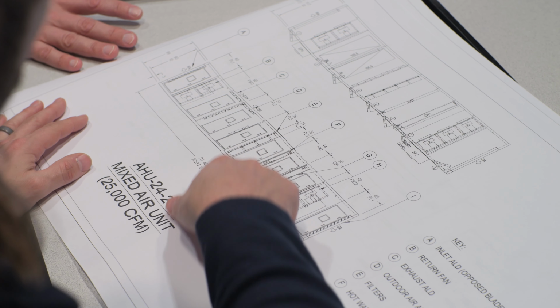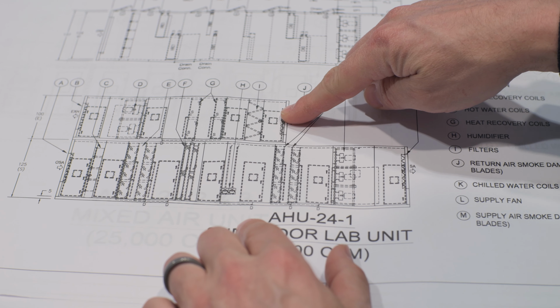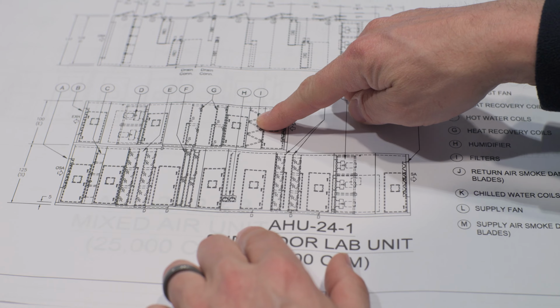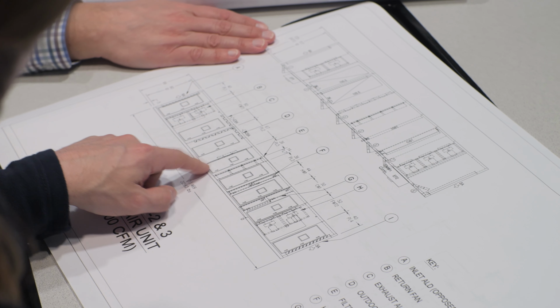A lot of GMP — Good Manufacturing Practice — is about making sure the cleanliness level is met. So we had to understand the ISO classification for each space and how many air changes were needed. An air change rate is the amount of air we're turning over in a space over time.